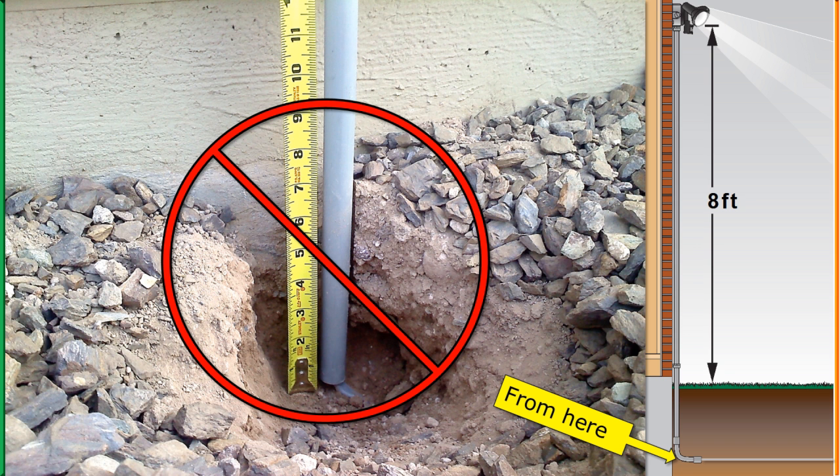And then look at our raceway. That's supposed to extend down to our minimum cover distance, but it never has to be any deeper than 18 inches. Both of these right now aren't any deeper than six or seven inches.